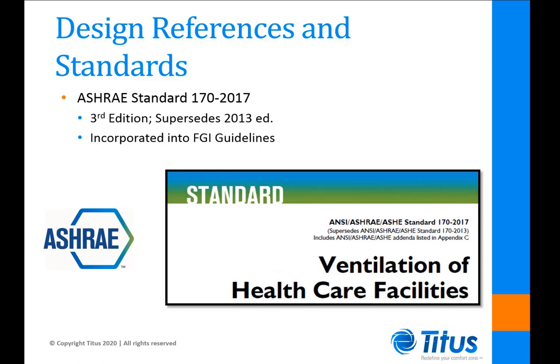Since the 2010 edition of the FGI guidelines, ASHRAE Standard 170 has been incorporated to address minimum engineering design criteria for HVAC systems. Since then, ASHRAE, ASHE, and the FGI guidelines have worked together to coordinate updates. The most significant recent change has been the addition of Sections 8 and 9 to ASHRAE Standard 170, addressing ventilation requirements for outpatient facilities in Section 8 and residential care facilities in Section 9, while Section 7 refines its focus to inpatient care spaces. The committee has been issuing addenda to update minimum design requirements for all healthcare facilities.